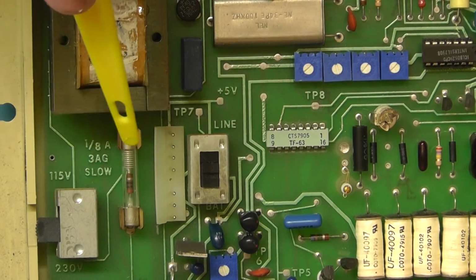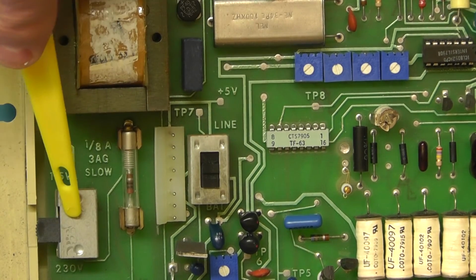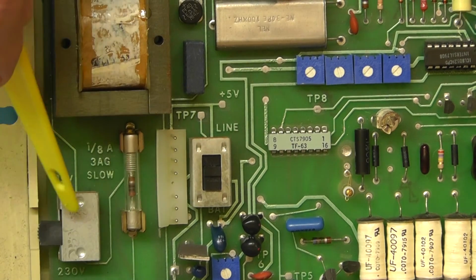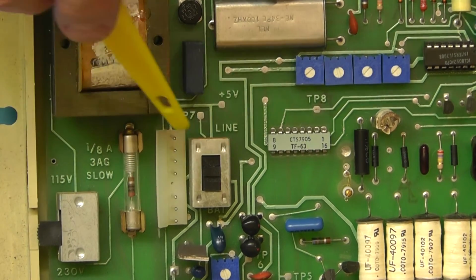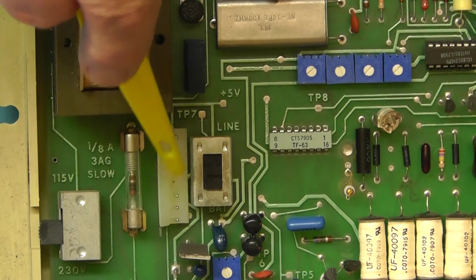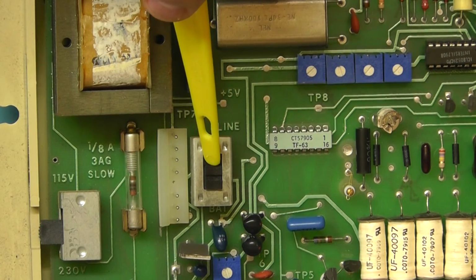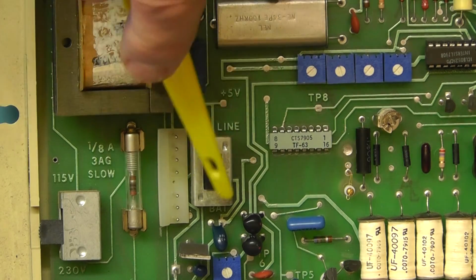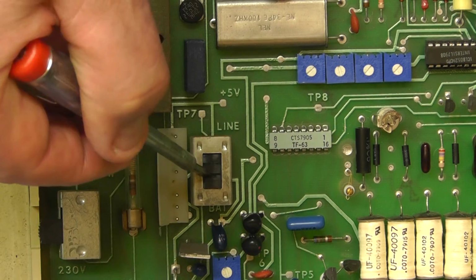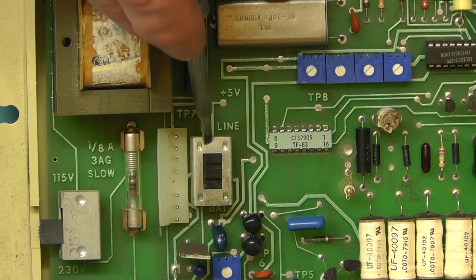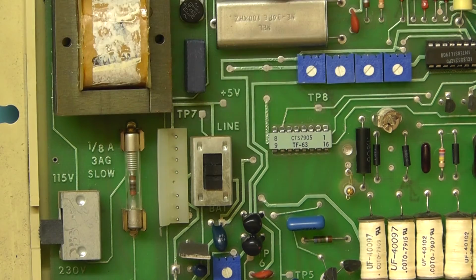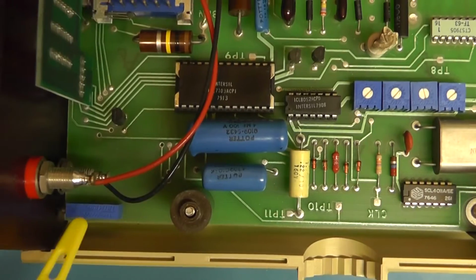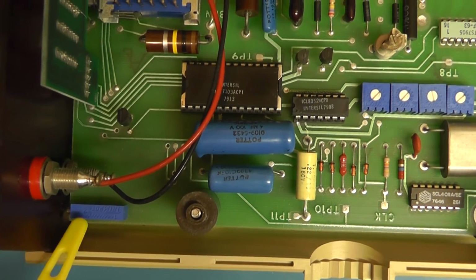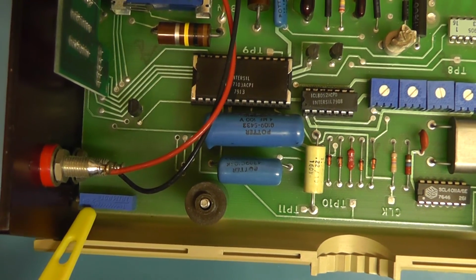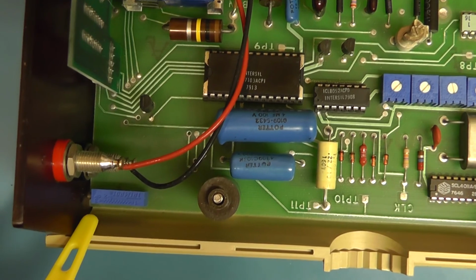Just a couple of points to note here at the back. This slider switch here is the mains selection switch for the mains transformer, either 115 volts or 230 volts, and that's the socket for the battery pack, and next to it you have the switch which can switch either battery pack in or battery pack out. If you don't have a battery pack, you have to have the switch in the line position, which is in this direction. With the battery pack in, you need to switch it the other way. In this corner of the meter we have the zero adjust preset, which is accessible through a slot in the front panel. That's just below the input connectors.